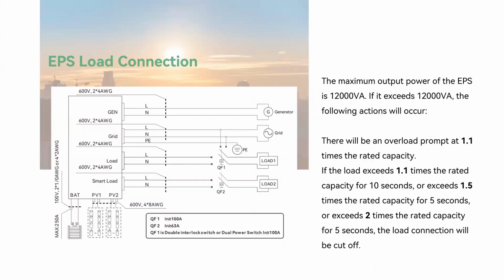As for the EPS load port, the maximum output power is 12 kilowatts, and the overload ability is 1.1 times the rated capacity for 10 seconds, and 1.5 and 2 times the rated power for 5 seconds. If it exceeds the time range, the load connection will be cut off.